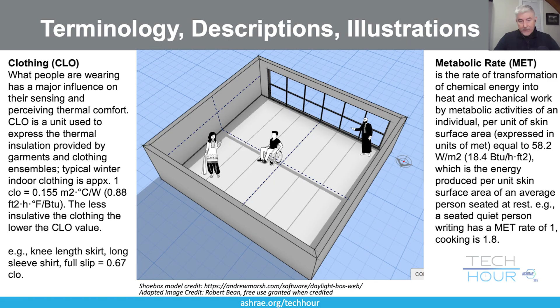One of the other important elements is what we call the mean radiant temperature, and I like to refer to it as the geometric thermal relationship that people have. For example, the individual next to the glass, if this was a cold climate, and that glass, even high performance glass, would be incredibly cold relative to his body. So his thermal relationship with that glass surface is going to be completely different than the lady on the corner of the building, where her relationship with the two interior surfaces is going to be much different.